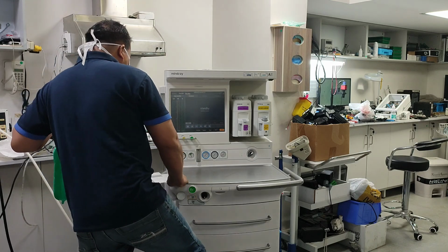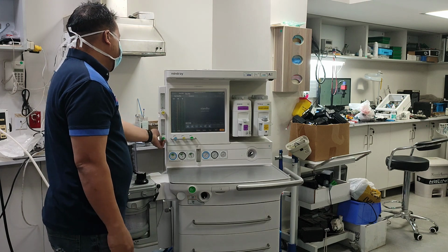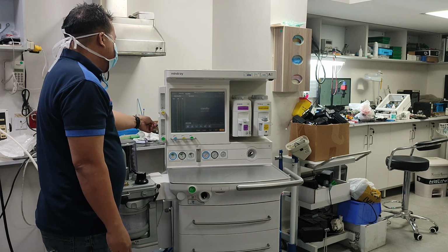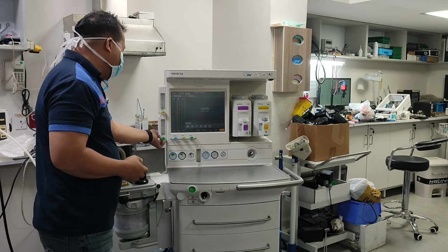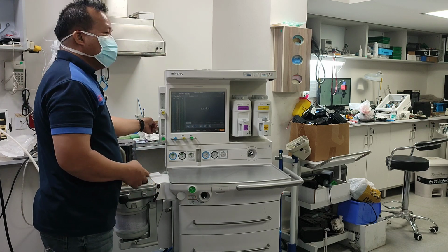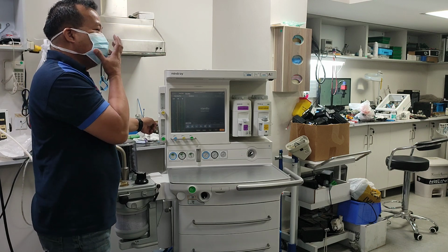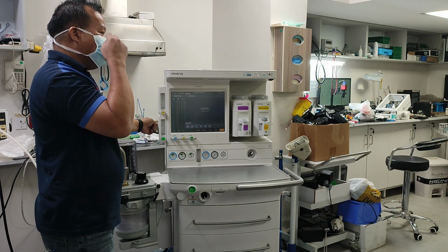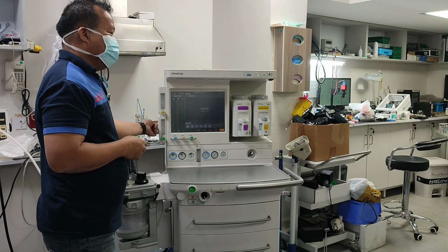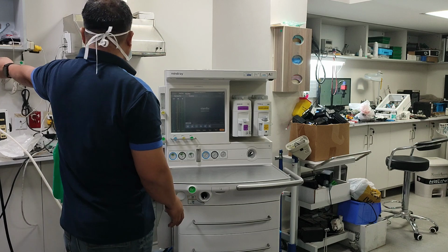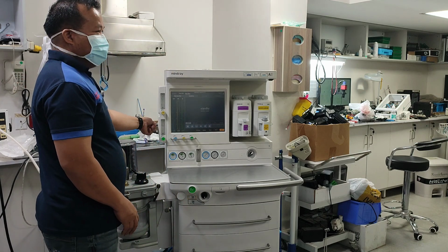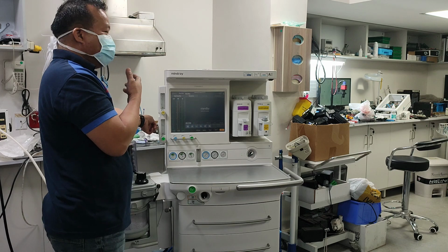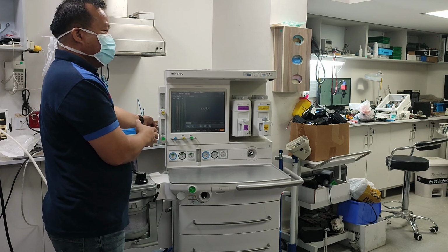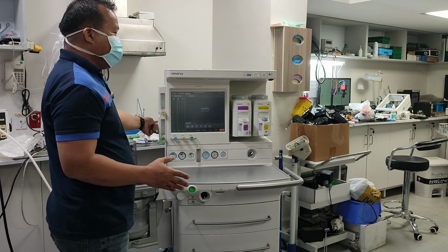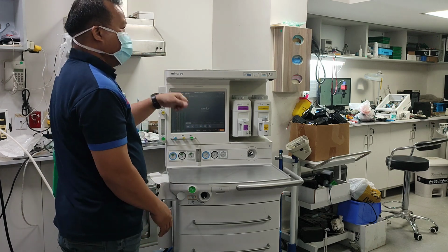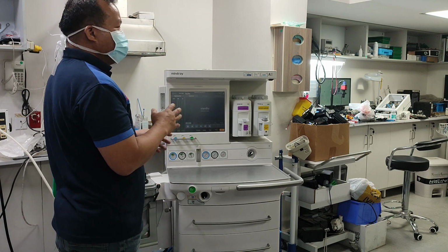So here we have the flow meter. What is the purpose of this flow meter? It is only for a patient who needs air, oxygen or a mixture of air, and does not need intubation. They need only air through a nasal mask. So this is the one you use. There is no need to put a cylinder or gas in this one. The anesthesia machine is already ready. For example, if the patient's saturation comes down and they need oxygen during the operation, they will connect this to the patient's nasal mask and support the oxygen through the nose.